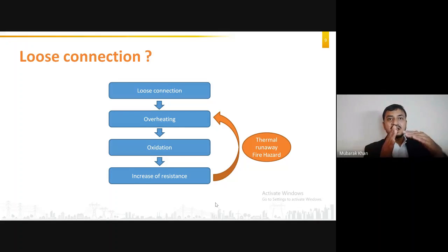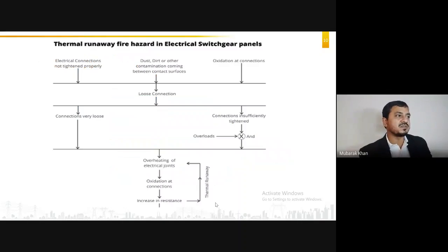Now in this bus bar condition, the bus bar is carrying 2000 ampere of current, and the bus bar is melting. What will happen? This 2000 ampere will try to continue to flow, and after the bus bar has gone, it will turn into an arc flash. That arc flash will damage anything and everything in the environment. So this is the hazard carried by loose connections in heavy current carrying applications.